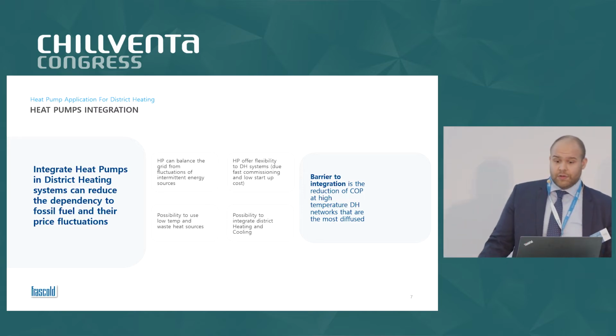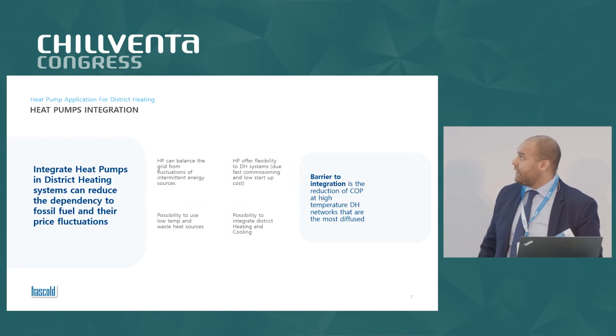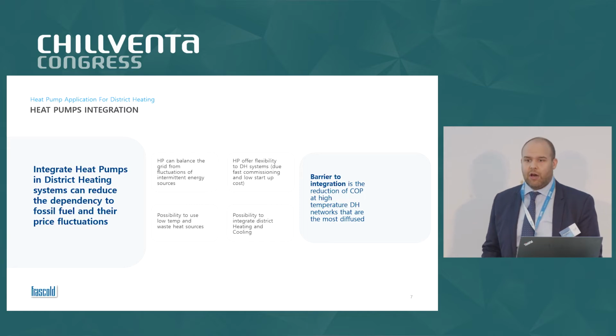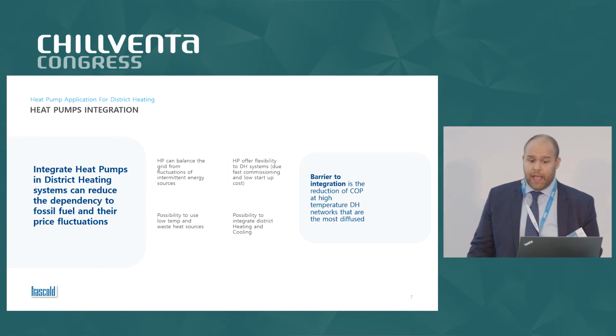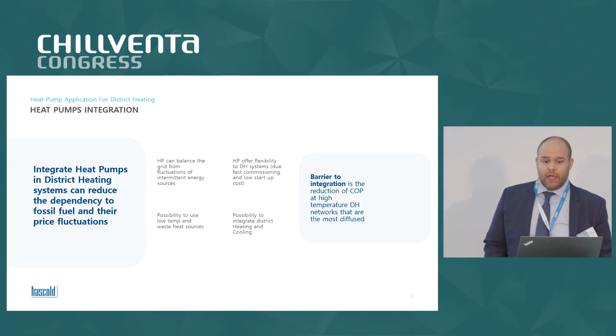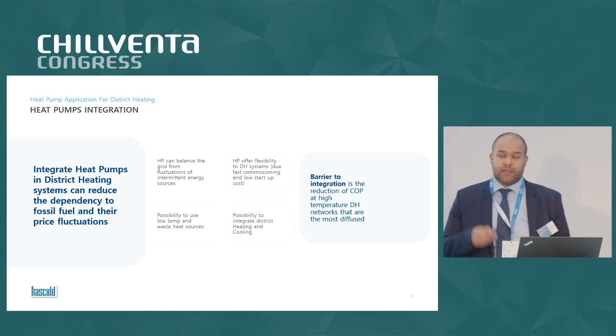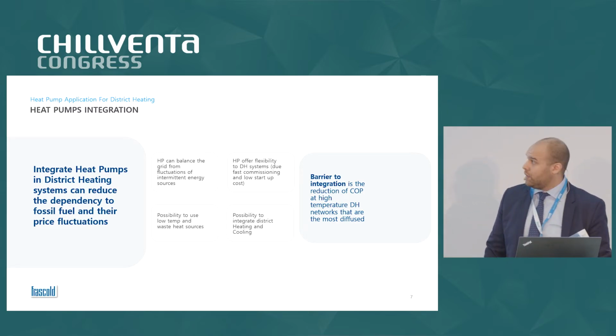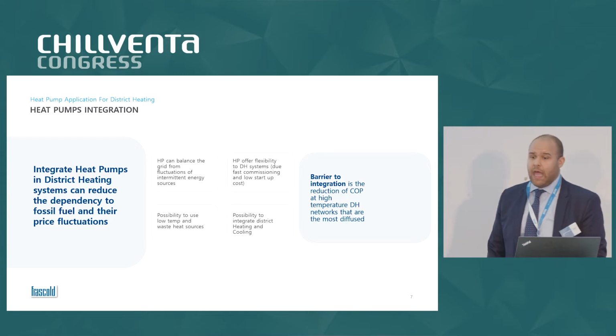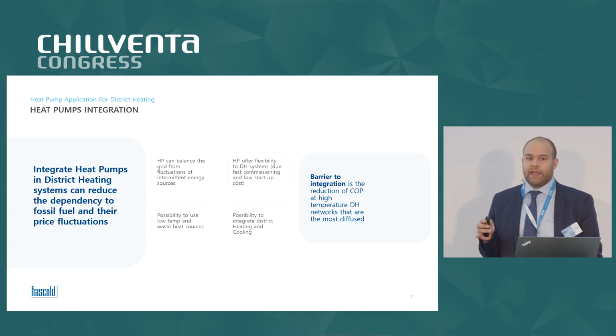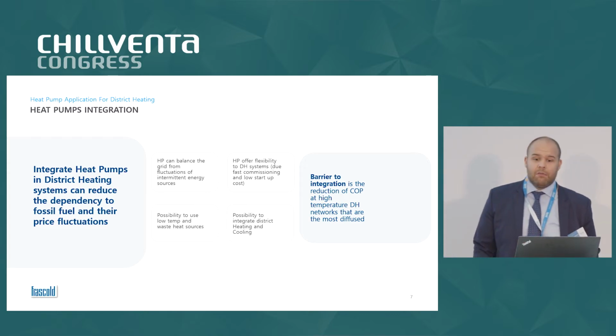They can also offer flexibility for the district heating system, thanks to the fast commissioning of heat pumps and the low startup cost compared to other technologies like gas boilers, wood chip boilers or something like that. And the possibility to use low temperature and waste heat sources for the production of heat in the heat pump. And clearly the possibility to integrate district cooling and district heating in the same system, that in some realities can be a strong point.